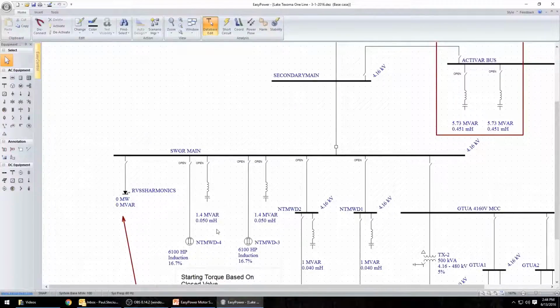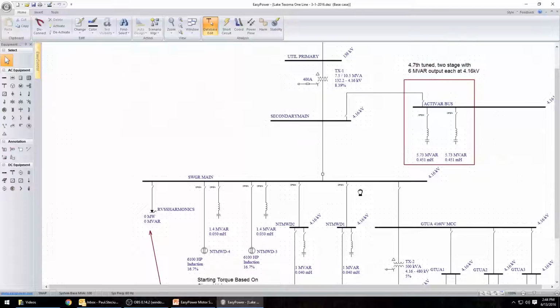When they went to start this facility with those soft starts, they found that they could not start the 6,100 horsepower motors because the short circuit level at this 4160 volt bus was too low. With the soft starts fully phased on, these motors here would not start. So the soft starts actually had no function here. With them fully phased on, the motors could not start. So the purpose of the actiVAR here was actually installed to support voltage to allow these motors to start, and that is the situation here.